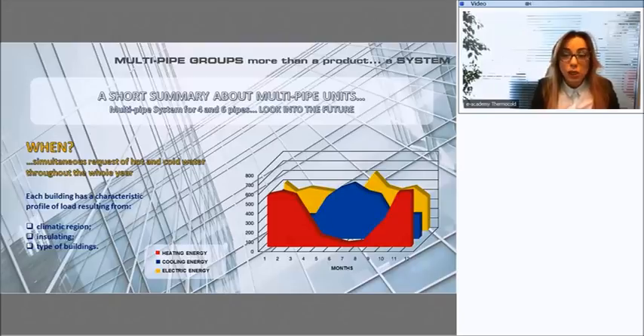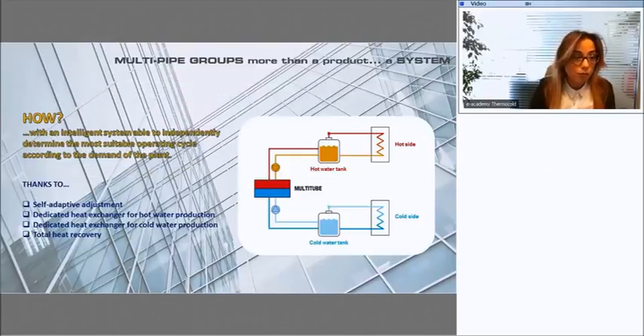As you may see from the graph, the cooling and heating load may change during the year, but also during the day in some specific applications. So for sure, a multi-pipe unit is the best solution if the building requires hot and cold water with a high variation during the year, but also during the day. How is it possible to satisfy this specific need? This is possible by using the multi-pipe unit.